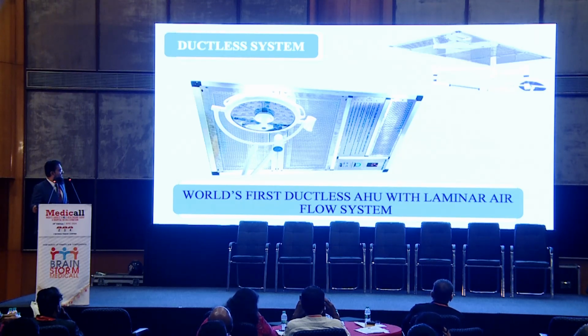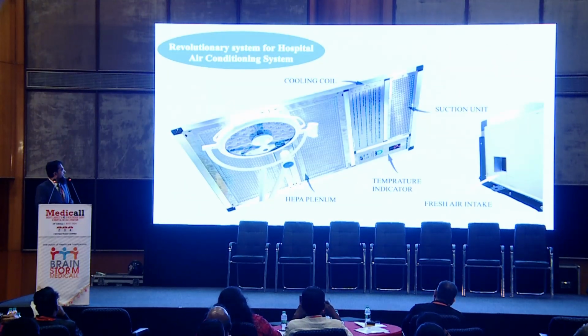Okay. See, this is the ductless system. I will take you through it first. This is the return area, sucking the air. 20% fresh air also comes into this chamber. In between there is the cooling coil. And this is the HEPA filter, the supply area. HEPA and activated carbon are also provided in this area.